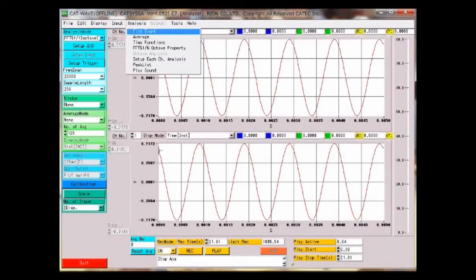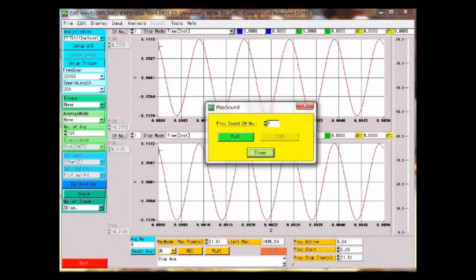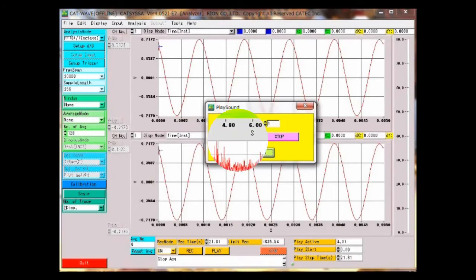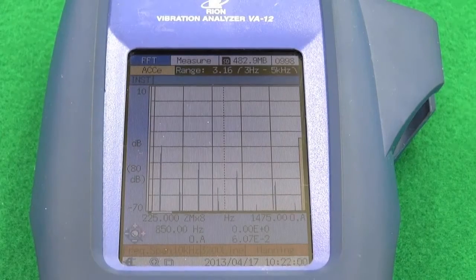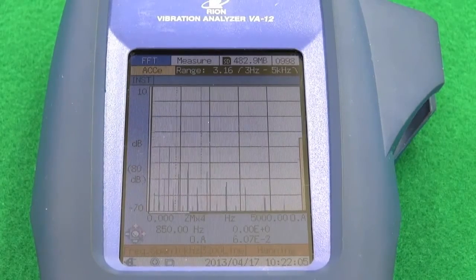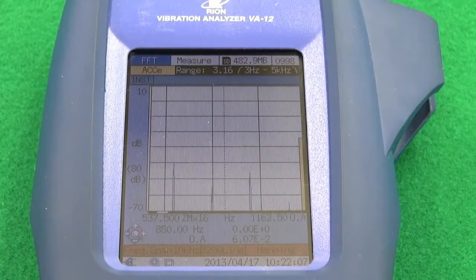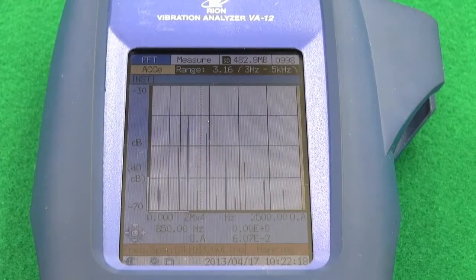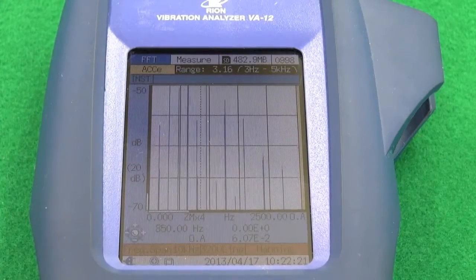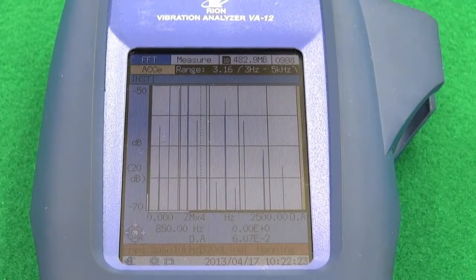Using dedicated analysis software, post-processing can be done using waveform file data from the VA-12. You can listen to the vibration sounds and judge and analyze them. The frequency axis can be magnified 2, 4, 8, or 16 times, and the magnitude axis can be magnified up to 1,024 times in FFT mode.